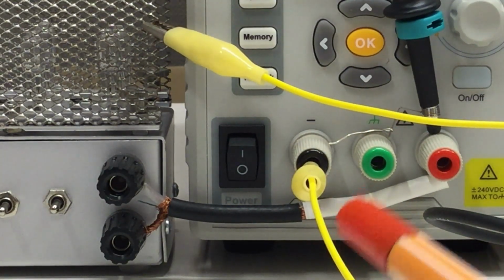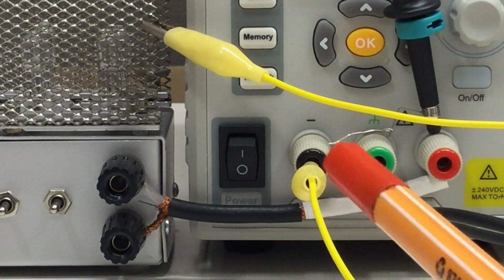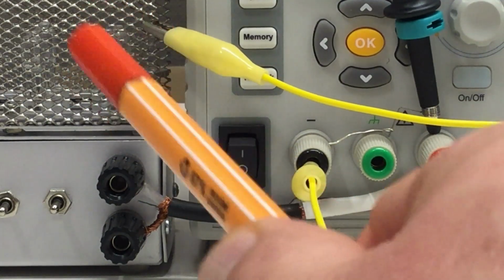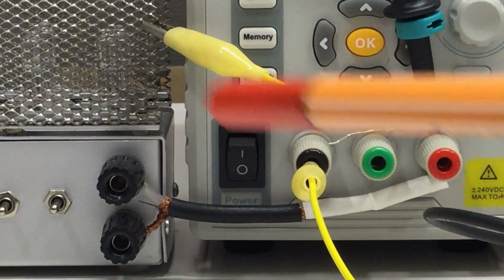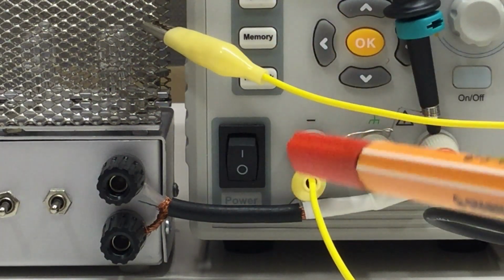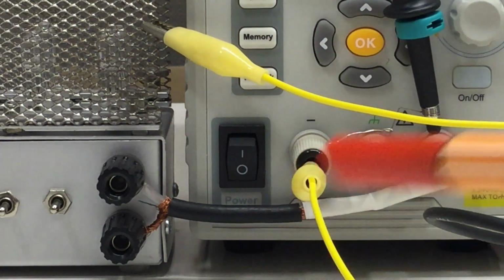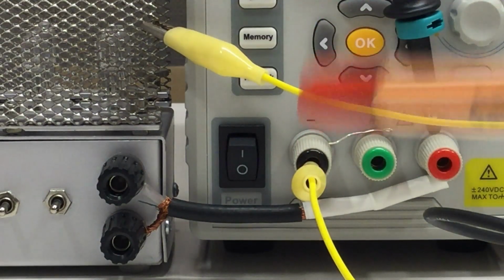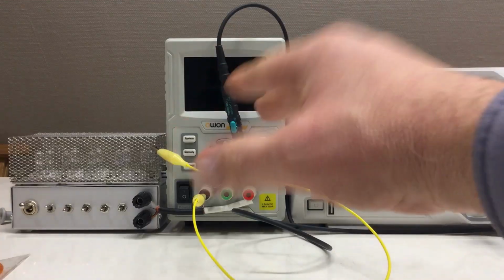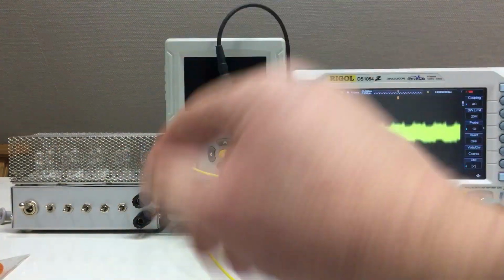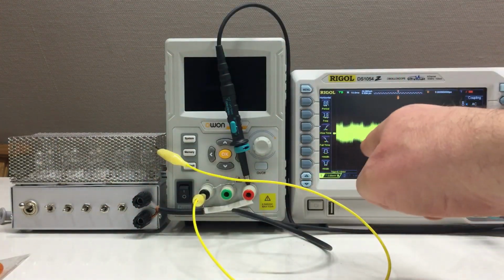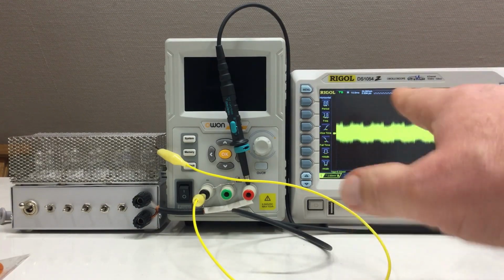And funnily enough, putting this yellow cable in here and basically connecting the frame of my load to ground helped also. What also helped was removing any 220 volts mains AC cables from the desk and putting them all on the ground. Okay, but it's probably not enough to see the noise generated by the power supply itself. But let's try. I found another unused but connected mains AC cable here somewhere in the corner and removed that. And now our noise level is down to 5 to 6 millivolts peak to peak.